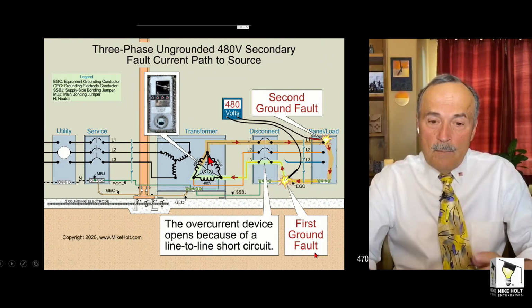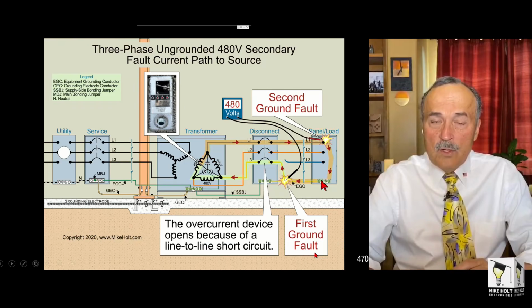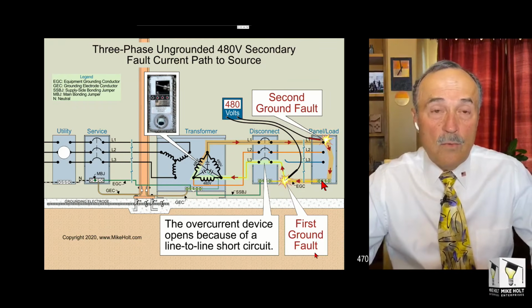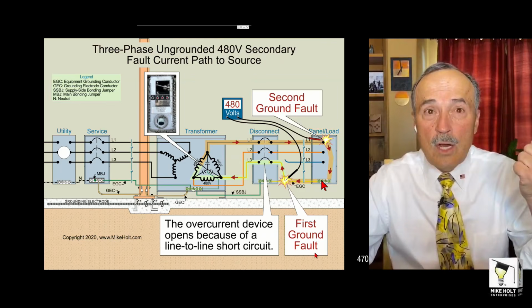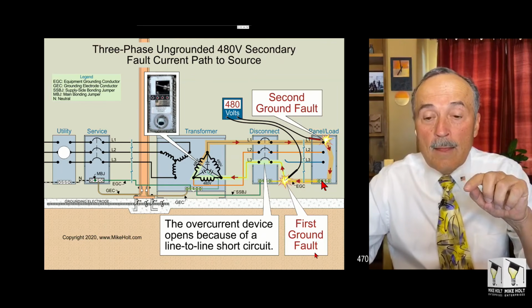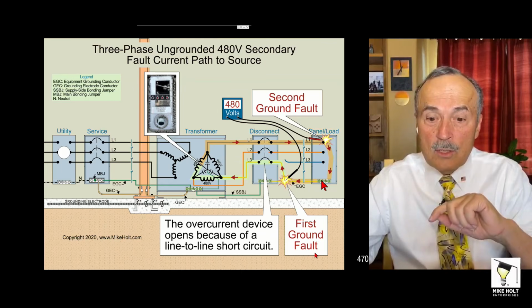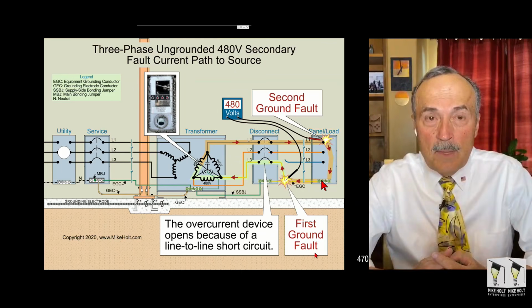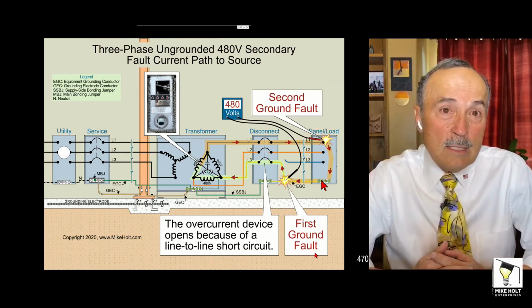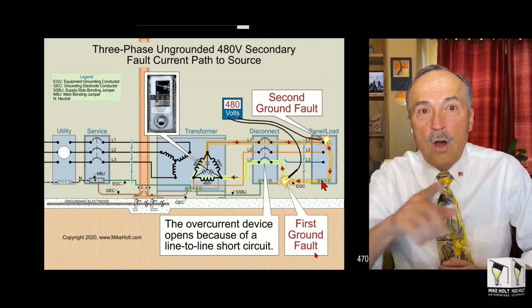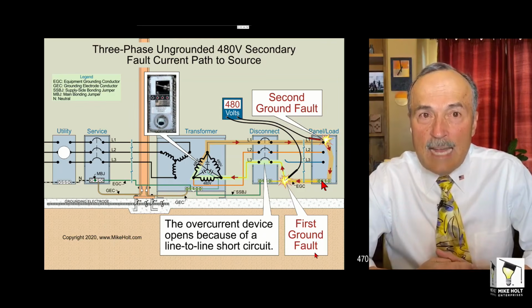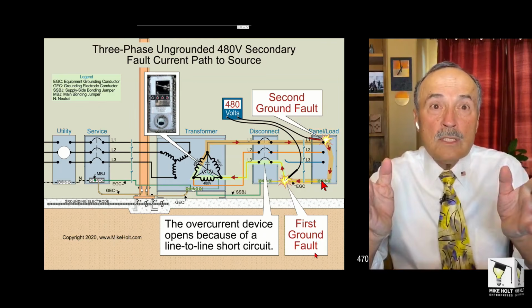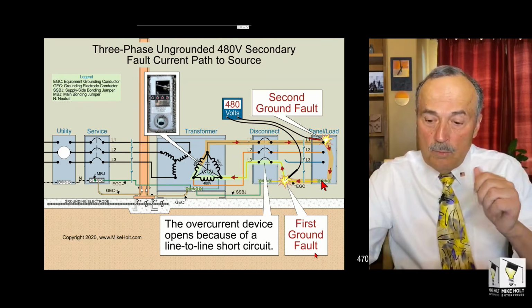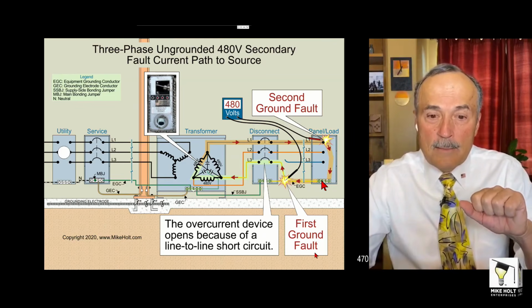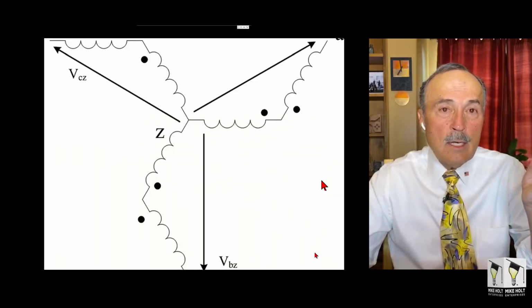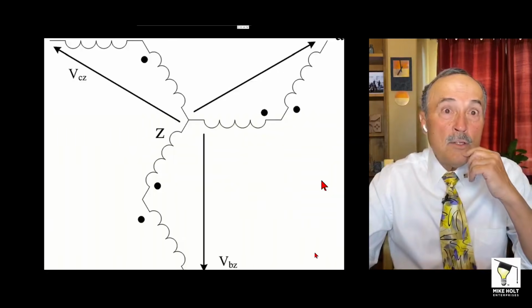How do you clear a ground fault? Well, if you have an ungrounded system, when there's the very first fault, then there is no fault current because it can't get back to the system. The ground detector goes off. If you don't clear the fault before a second fault occurs, now you have a phase-to-phase fault. That's why the code says for ungrounded systems that you have to make sure all the metal parts are bonded together, just as if it were a grounded system, so that all those metal parts would serve as an effective ground fault current path.